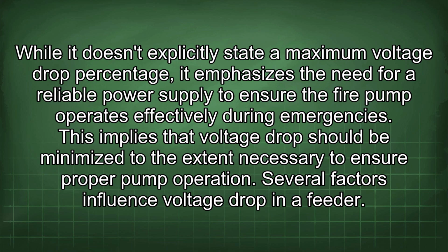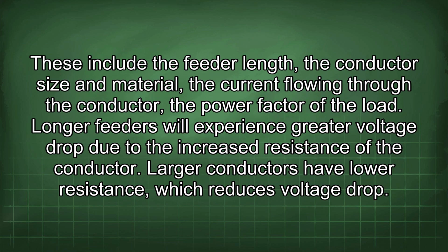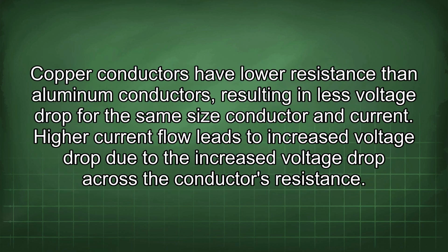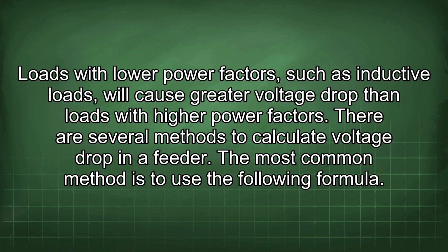Several factors influence voltage drop in a feeder. These include the feeder length, the conductor size and material, the current flowing through the conductor, and the power factor of the load. Longer feeders will experience greater voltage drop due to the increased resistance of the conductor. Larger conductors have lower resistance, which reduces voltage drop. Copper conductors have lower resistance than aluminum conductors, resulting in less voltage drop for the same size conductor and current. Higher current flow leads to increased voltage drop across the conductor's resistance. Loads with lower power factors, such as inductive loads, will cause greater voltage drop than loads with higher power factors.